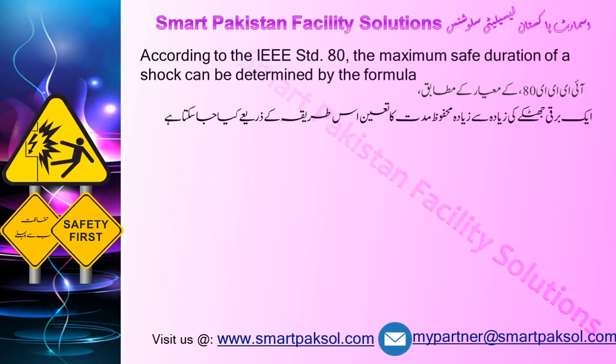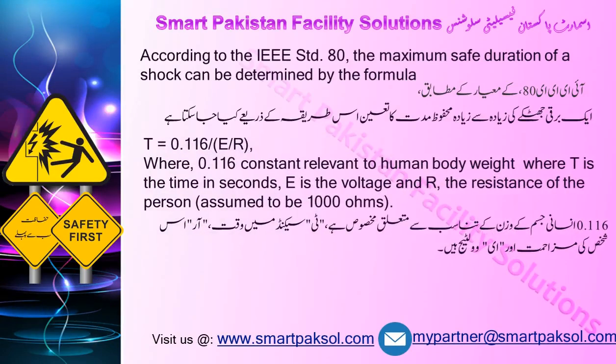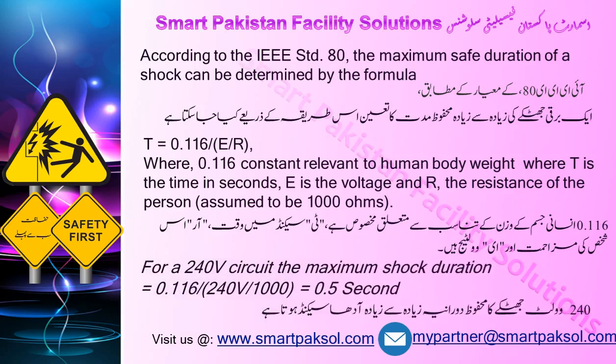According to IEEE Standard 80, the maximum safe duration of a shock can be determined by the formula given. Where 0.116 is a constant relevant to human body weight, T is the time in seconds, E is the voltage, and R is the resistance of the person, assumed to be 1000 ohms. For a 240-volt circuit, the maximum shock duration is half of a second.